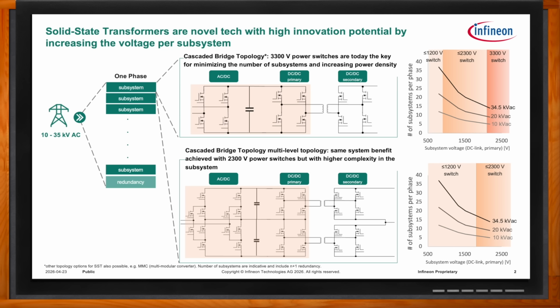For sure. So, in principle, there are many different kinds of SSTs in the making. In our context, we talk about SSTs for AC to DC conversion, and we have many new energy applications now out there which are DC and connected to an AC grid. Today, so-called medium voltage line frequency transformers step down the voltage from a medium voltage level to a lower level, and then there is a conversion from AC to DC. The target of an SST is now to replace this transformer using latest power electronics and semiconductor technology instead. There are a bunch of advantages compared to this traditional approach, namely better controllability, better efficiency, shorter lead times, and things like that. So it's a very attractive new application.